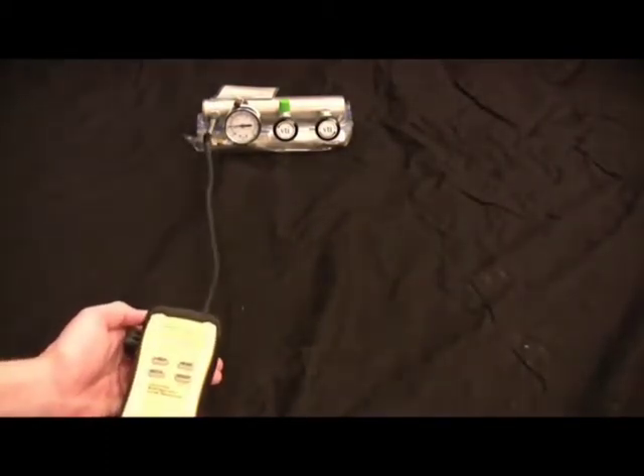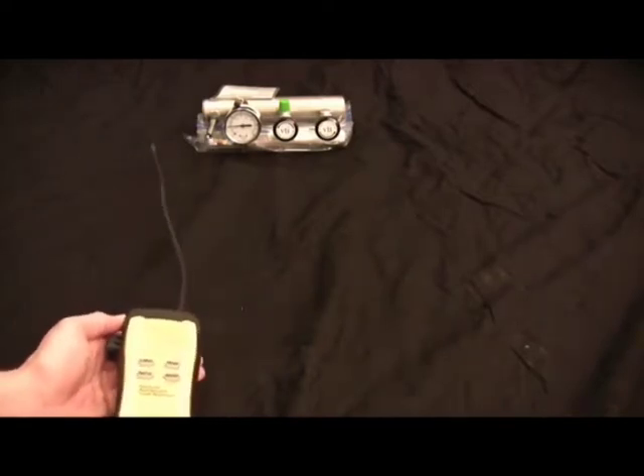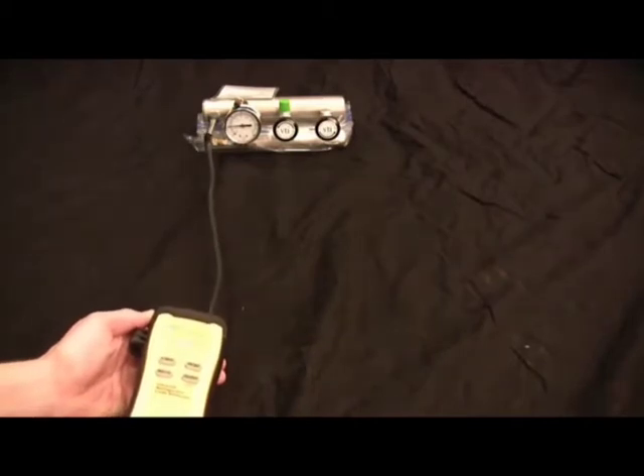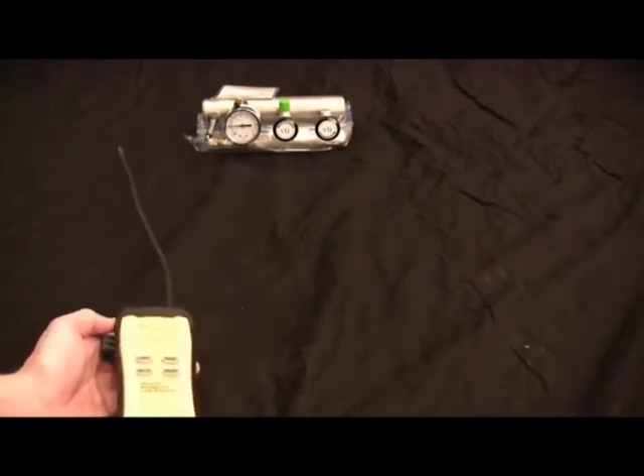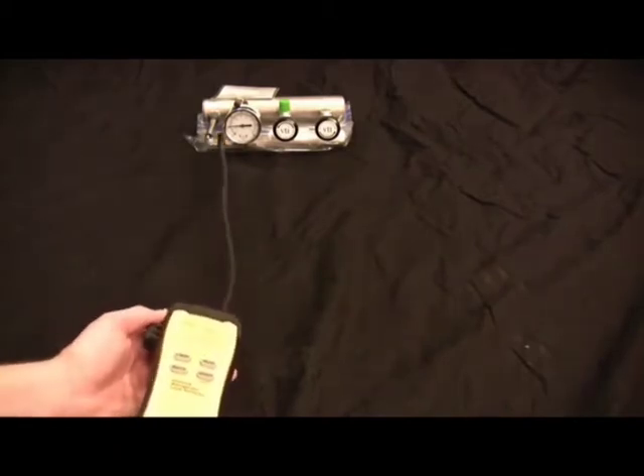Now also what's nice about the infrared leak detectors is they don't go off on oil or moisture. So I have a little bit of oil, refrigerant oil right here. I'm just going to refresh it with this bottle of oil. Just so we have, make sure that we have brand new fumes to try to detect. Now a lot of heated diodes will go off on refrigerant oil.